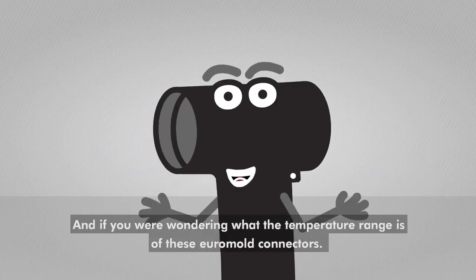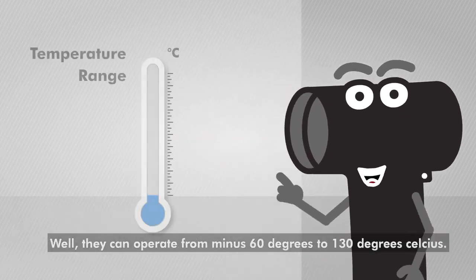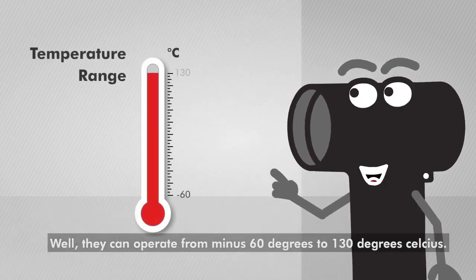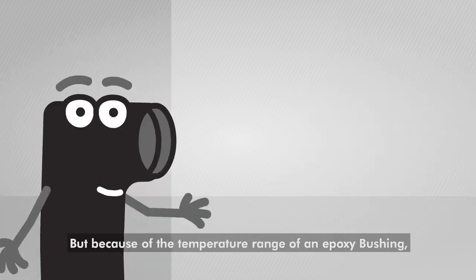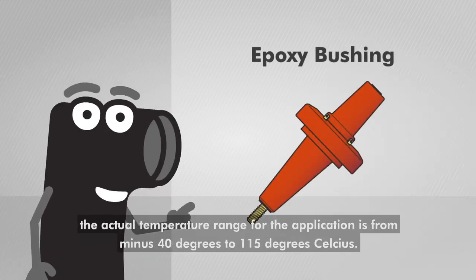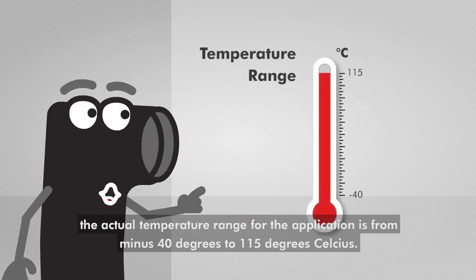And if you were wondering what the temperature range is of these Euromold connectors, well they can operate from minus 60 degrees to 130 degrees Celsius. But because of the temperature range of an epoxy bushing, the actual temperature range for the application is from minus 40 degrees to 115 degrees Celsius.